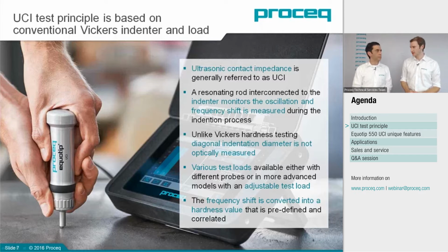For the test load, there are different loads used for different applications. You have already mentioned that there are different test loads available. Our probe is special as we have an adjustable test load. Other probes are usually fixed with one certain test load, but then there are different versions available with different test loads. Usually these loads range from HV1, or about 10 newtons, up to 50 newtons, or HV5.